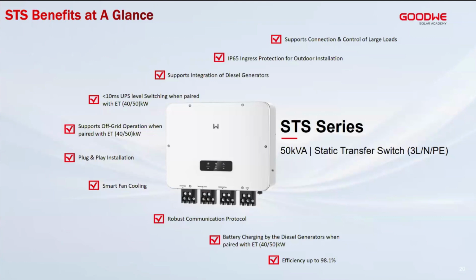Now, I mentioned before the ET series. For the African market, because we would like to utilize the backup or off-grid functionality of the inverter, the ET series, the 40 and the 50 kilowatts, will need to be connected to the STS. The STS is basically a smart transfer switch, or, if you may put it, a smart automatic transfer switch for this market. So why is it very unique?